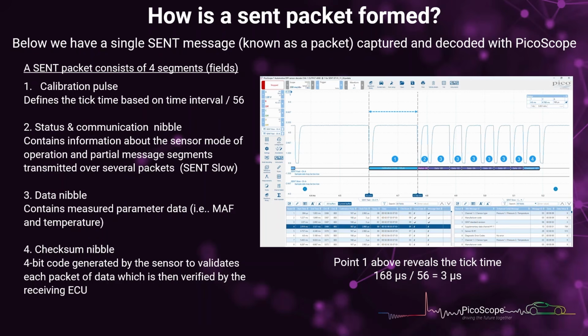And here we are, on the right hand side, point 1, we're measuring the calibration pulse. Notice where we're measuring from, edge to edge. That's falling edge, not rising edge. Falling edge is much crisper than a rising edge. Edge to edge, and the same for every subsequent pulse.